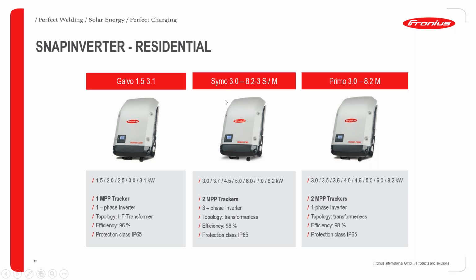Okay, so let's move ahead to the Symo, a small Symo that ranges from power class of 3 to 8.2. We have them in 3, 3.7, 4.5, 5.0, 6, 7, and 8.2 kilowatts. This time around, it has 2 MPPT trackers. It's a 3-phase inverter, and it's a transformerless inverter. As you can see, it has an increased efficiency compared to the transformer-based inverter. Its efficiency is 98%, and it also has a protection class of IP65.